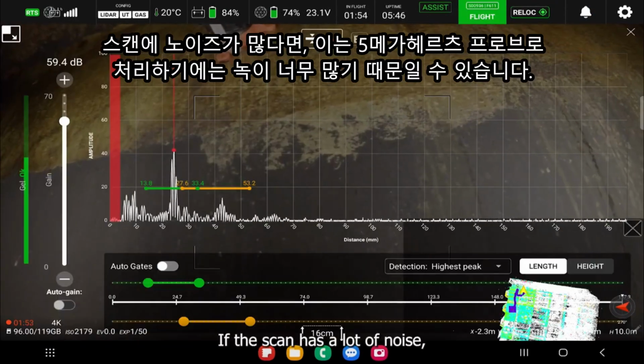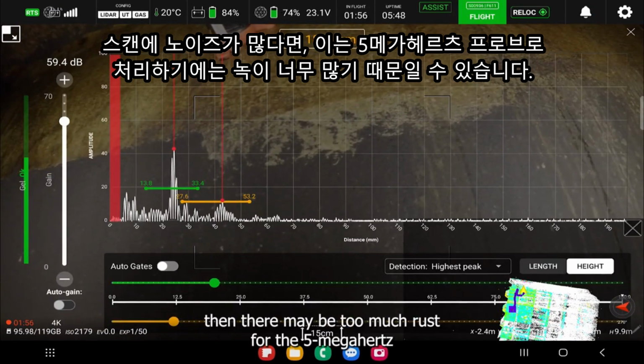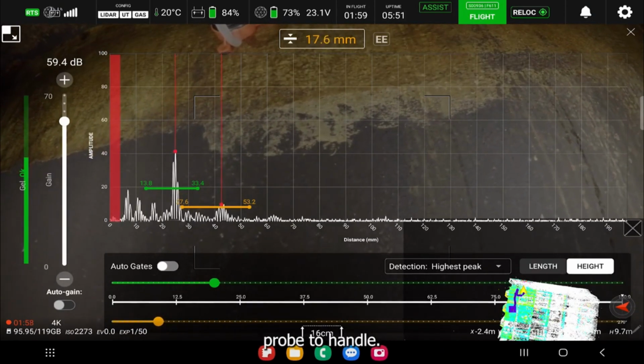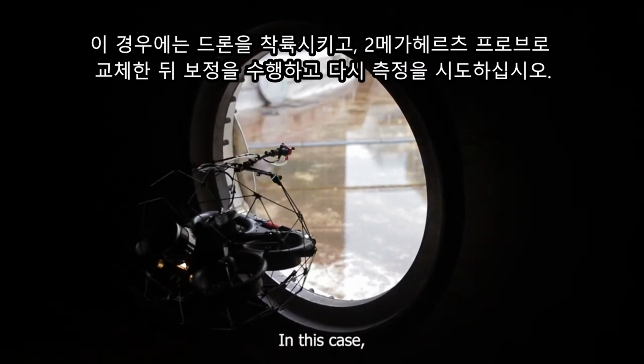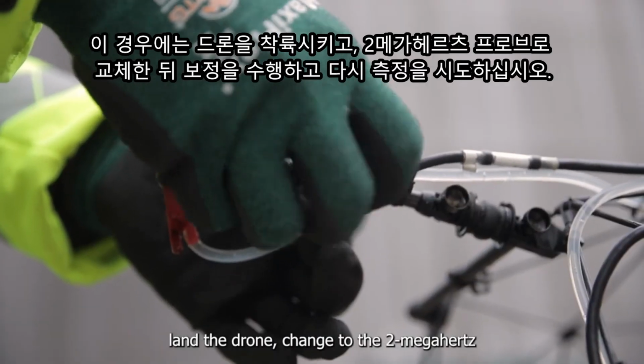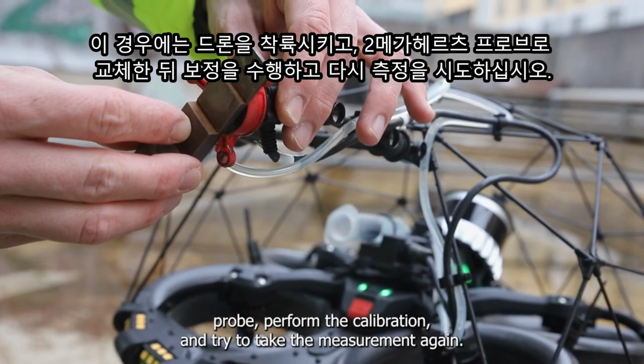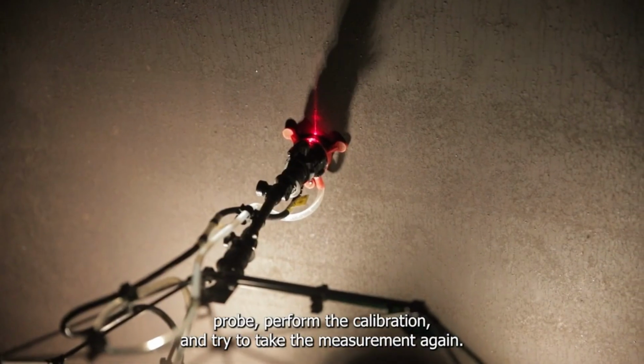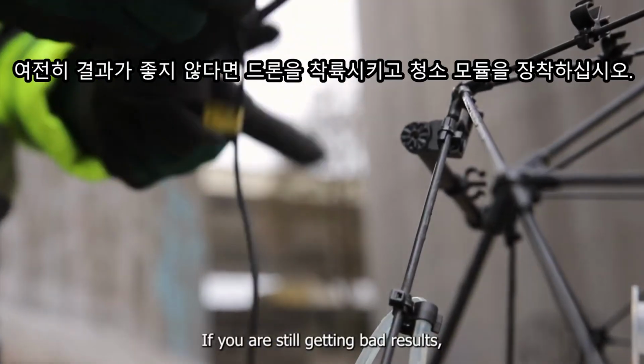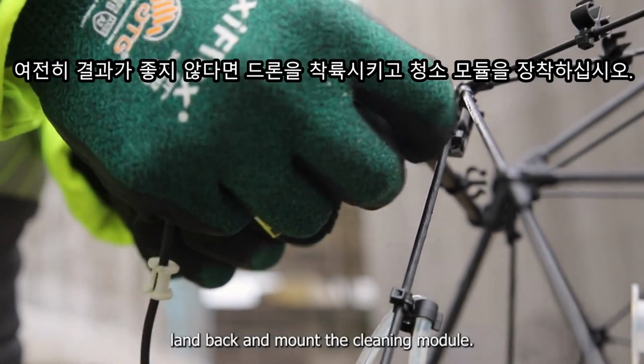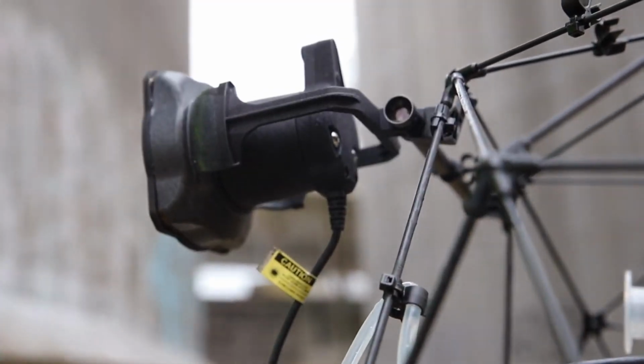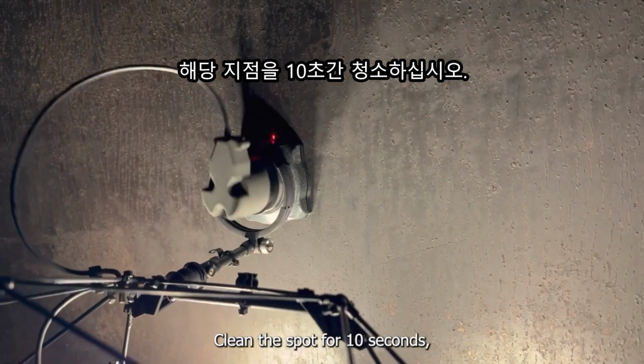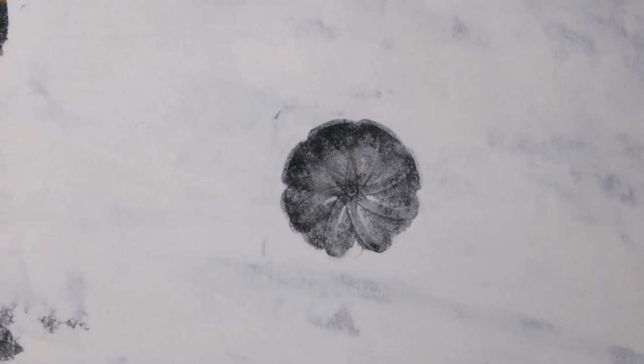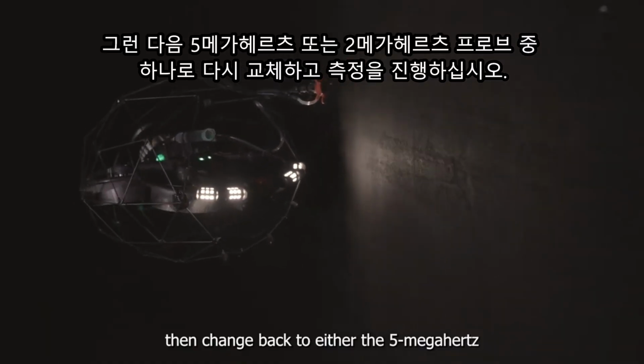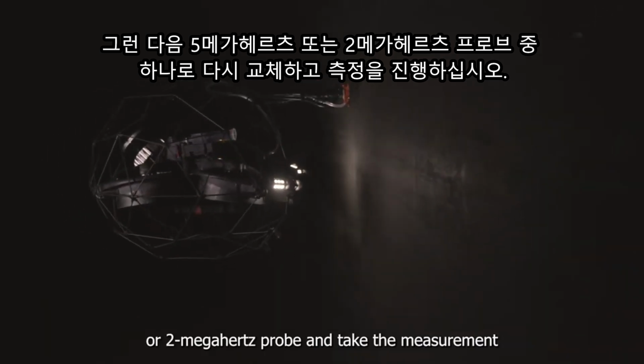If the scan has a lot of noise, then there may be too much rust for the 5 MHz probe to handle. In this case, land the drone, change to the 2 MHz probe, perform the calibration, and try to take the measurement again. If you are still getting bad results, land back and mount the cleaning module. Clean the spot for 10 seconds. Then change back to either the 5 MHz or 2 MHz probe and take the measurement.